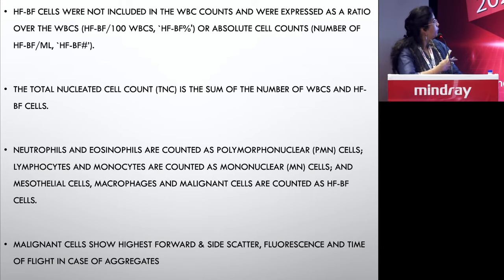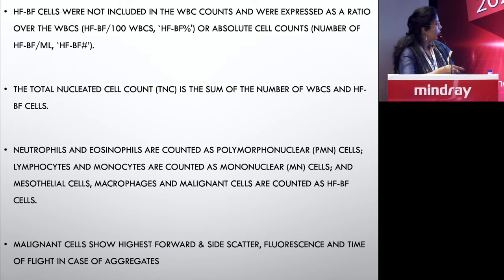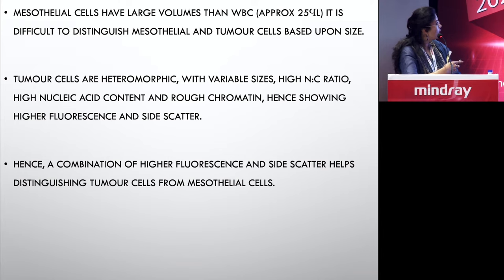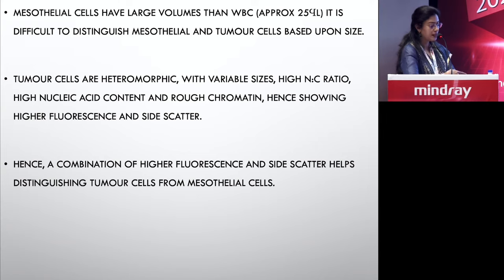High fluorescent body fluid cells are not included in the WBC count; they are expressed as a ratio to WBCs or as an absolute cell count. Total nucleated cell count is the sum of WBCs and high fluorescent body fluid cells. Neutrophils and eosinophils are counted as polymorphonuclear cells; lymphocytes and monocytes as mononuclear cells; and mesothelial cells, macrophages, and malignant cells together appear in the high fluorescent body fluid area. A combination of high fluorescence and side scatter is very useful to distinguish tumor cells from mesothelial cells.